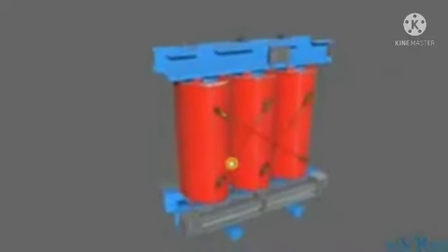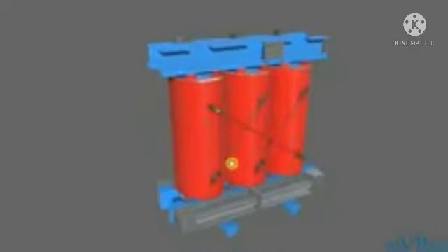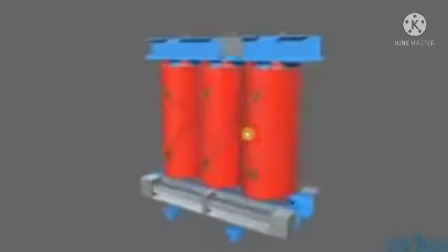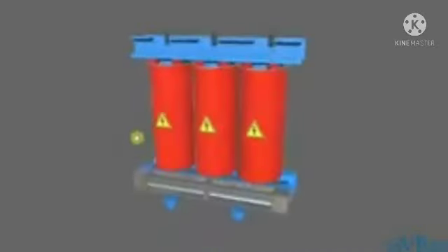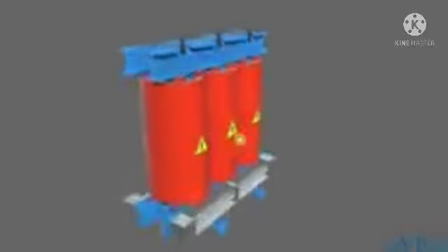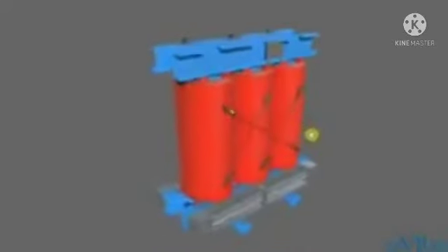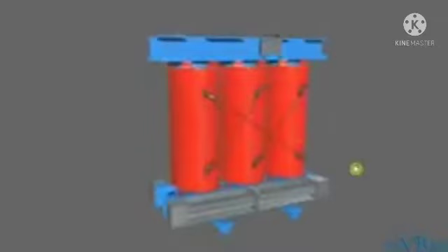But just remember, low voltage windings are going to be wrapped first around the core. High voltage windings are going to be wrapped second around the low voltage windings themselves. And then we're going to assemble the whole thing together. The windings themselves are going to be either copper or aluminium. And that is our transformer as we have it now. The core and the windings are the most essential pieces of the transformer. Technically, you can even manufacture a transformer without the core, although it will not be very efficient.